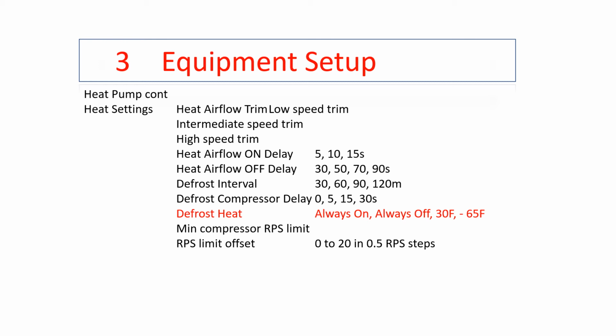Under the heat pump portion of the settings, we'll have our heat airflow on delay or off delay, and we'll have our defrost interval. The defrost interval is set for 30, 60, 90, or 120 in minutes. And keep in mind, if you set it for 60, that's 60 total minutes of runtime when the defrost sensor is under 32 degrees. Our defrost compressor delay can be set in seconds if we have a whooshing sound or an abnormal sound, a noise that may bother the customer when it's going from heating to cooling. We can set the delay where we can move the reversing valve and bring on the compressor separately where we won't get the whoosh sound.